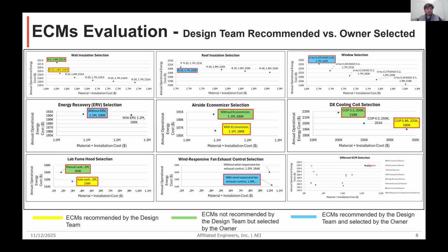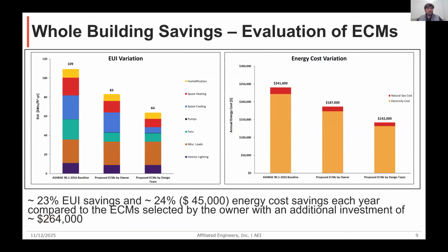Before moving on to the next slide, I'll rephrase this slide by saying that some of the options were aligned with the owner selection, but others were not, because the owner had a preference for the lowest first cost, which is not bad from their perspective, as they had pretty tight cost constraints for the project. Now I'll talk about the savings from a whole building perspective. The left chart is showing the variation of EUI, energy use intensity, in kBtu per square foot per year for three cases. The first case is the ASHRAE 90.1 2016 baseline. The second case is the proposed ECMs that were selected by the owner. And the third case is showing the options that are recommended by the design team.